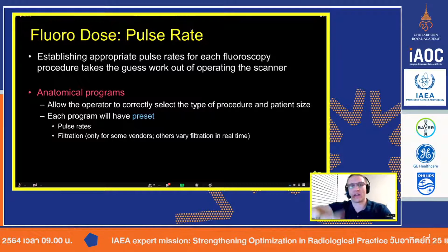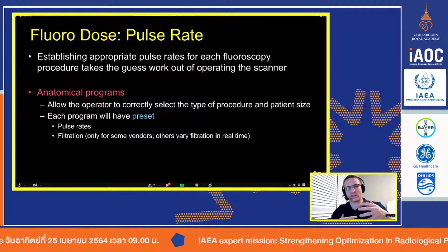And higher filtration equals larger focal spots. That means your spatial resolution goes down. So there are trade-offs. If you're going to be imaging a little kid, maybe you're doing something in the heart, you don't want to use a lot of filtration because then you might not have the resolution necessary to see the very small vasculature that you need to see. And then obviously you need to make sure the system is set so that, based on patient size, maybe the grid is already selected to be out versus grid in. We talked about the pros and cons of grids last week.